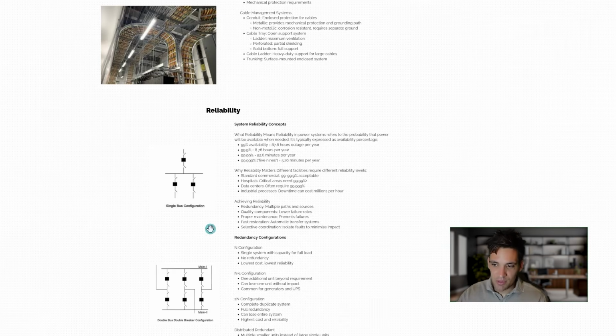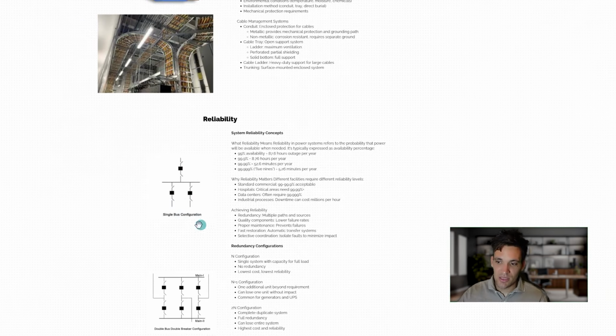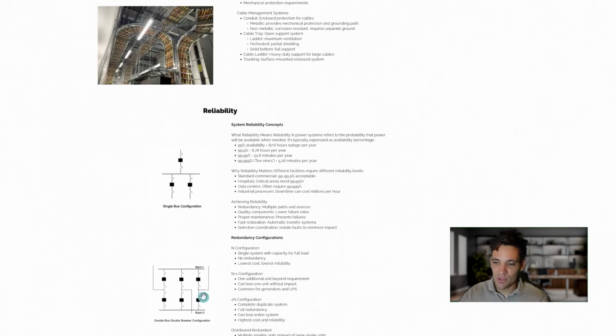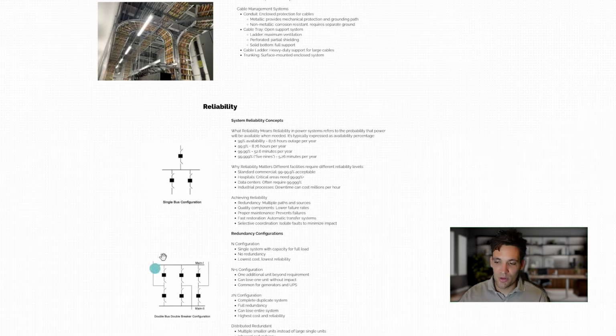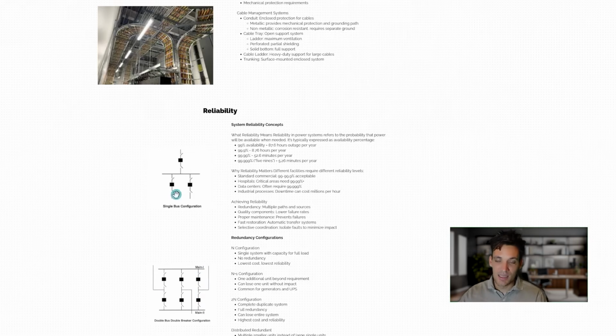So we're talking about how much reliability can impact design. If we look at a simple substation design that's a single bus configuration, it means you have one incoming circuit and two outgoing circuits. If you lose the bus bar or any of the circuit breakers, the system drops off. When you talk about a highly reliable design, you could have a double bus, double breaker configuration, which means you have two bus bars. If you lose either bus bar, the second bus bar can still operate. Each of the incoming lines has two circuit breakers, so if one circuit breaker goes down for whatever reason, you still have the secondary breaker. So you can see every component has a second reliable component, and that will have a much higher level of reliability than the single bus system.